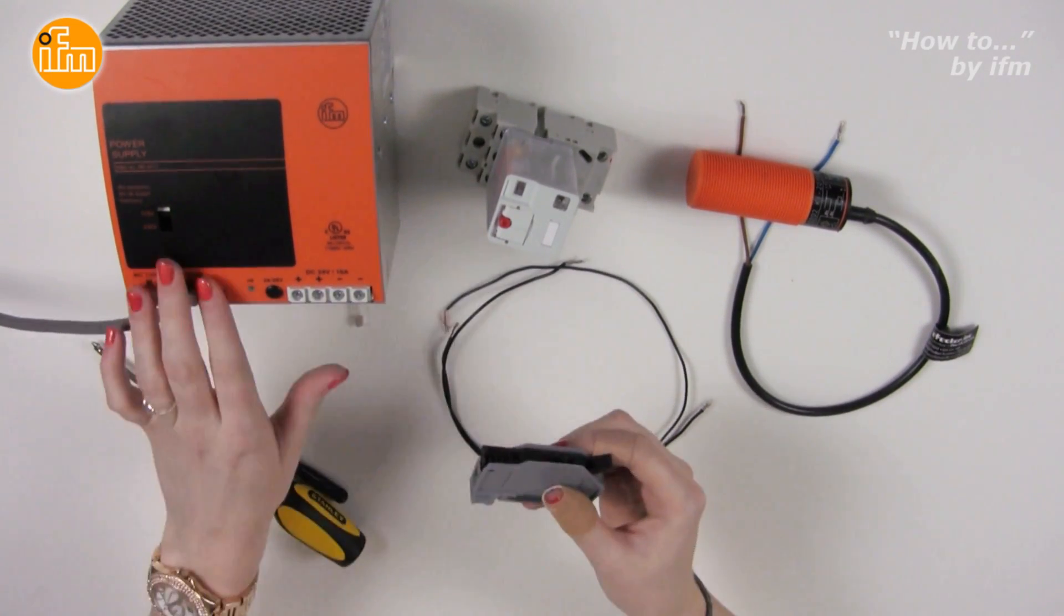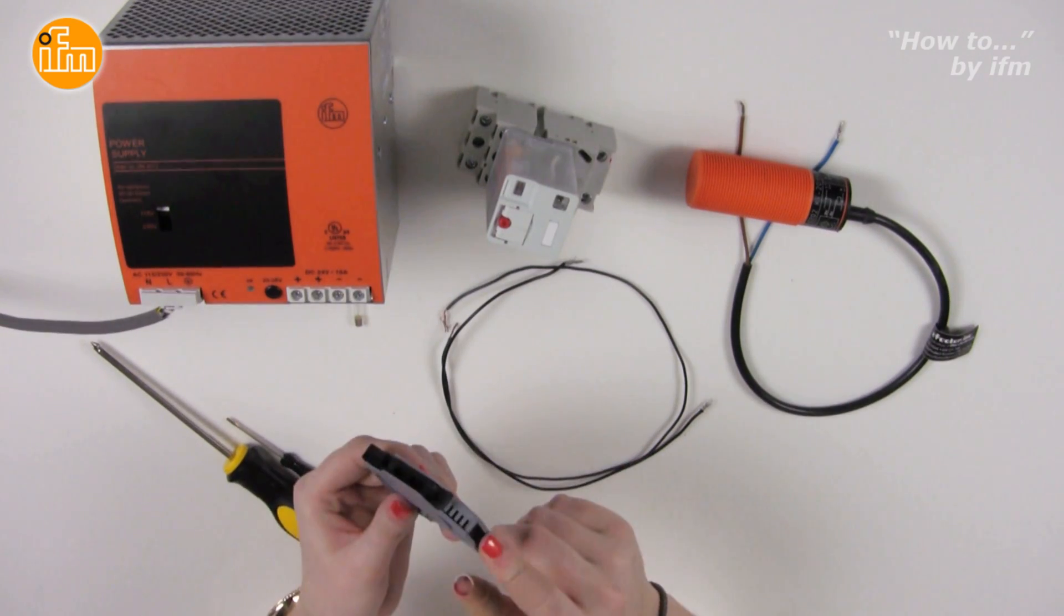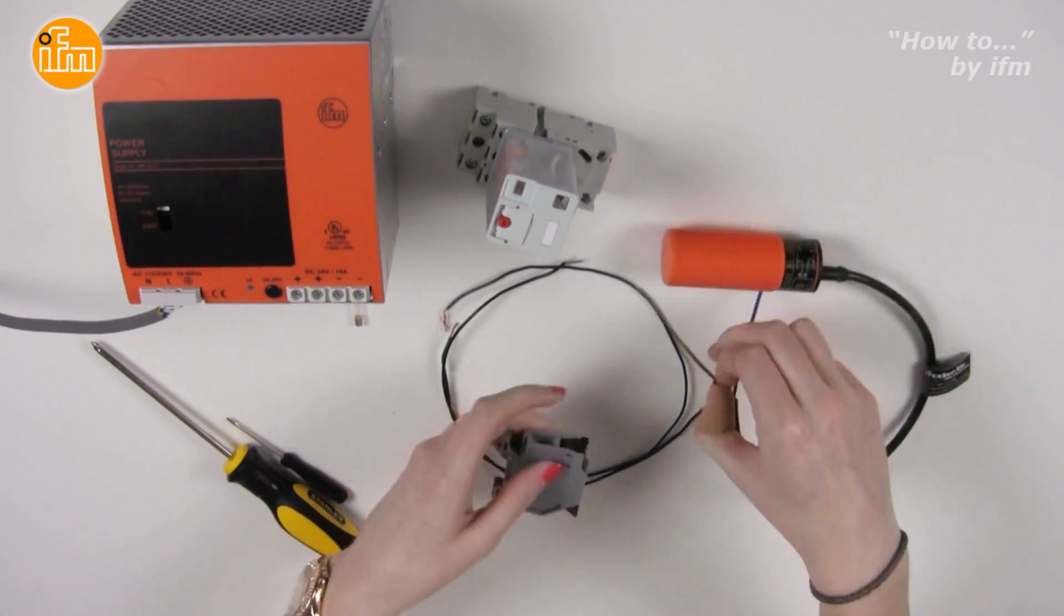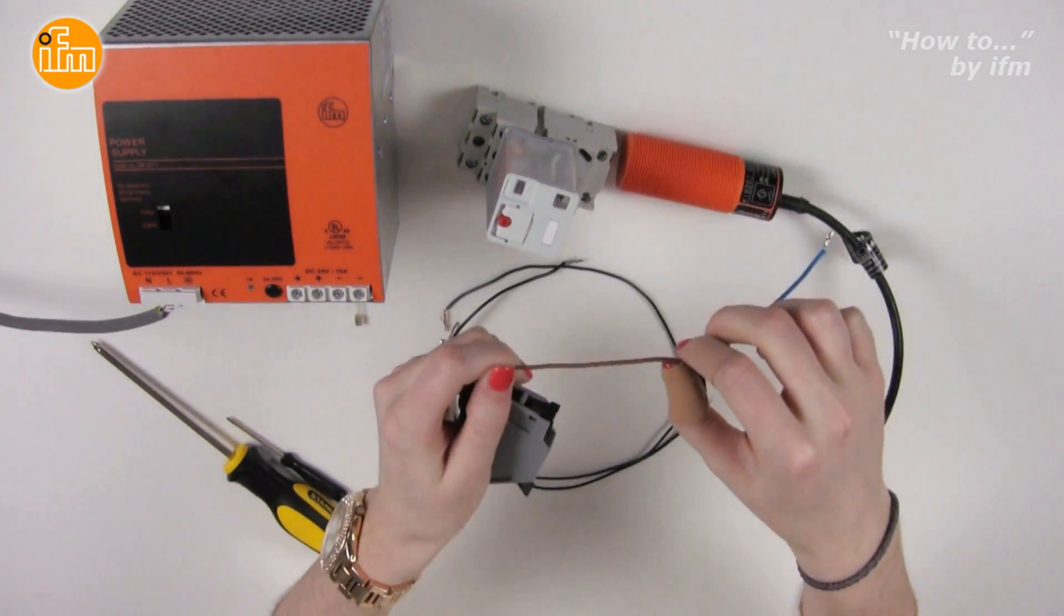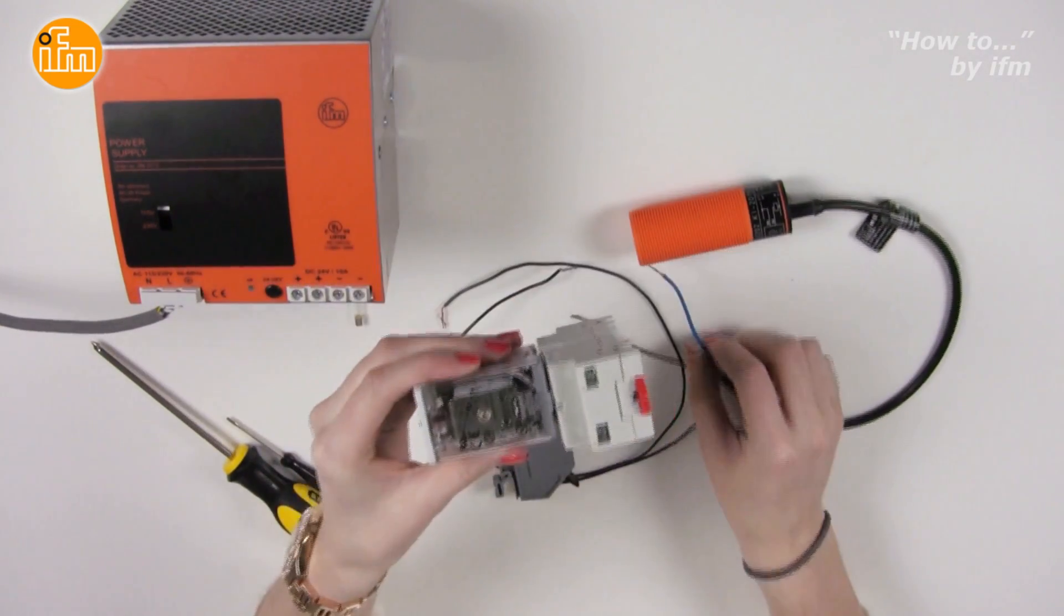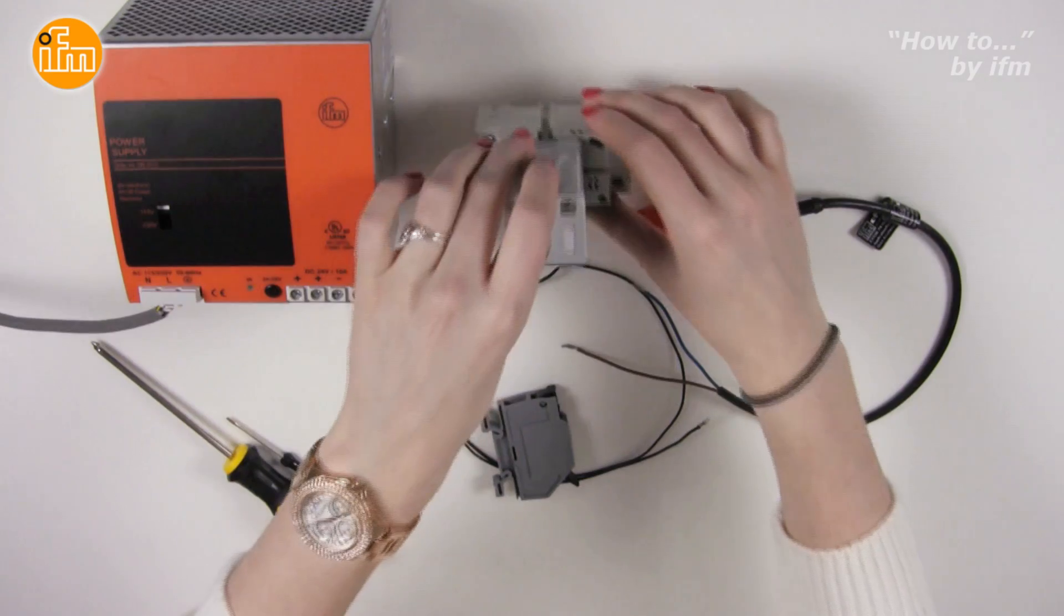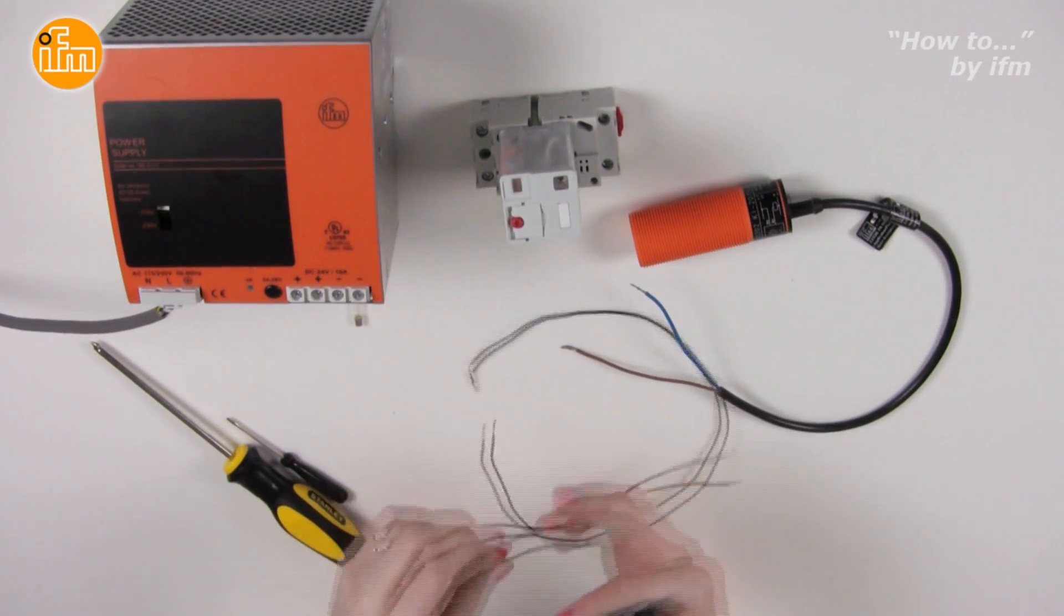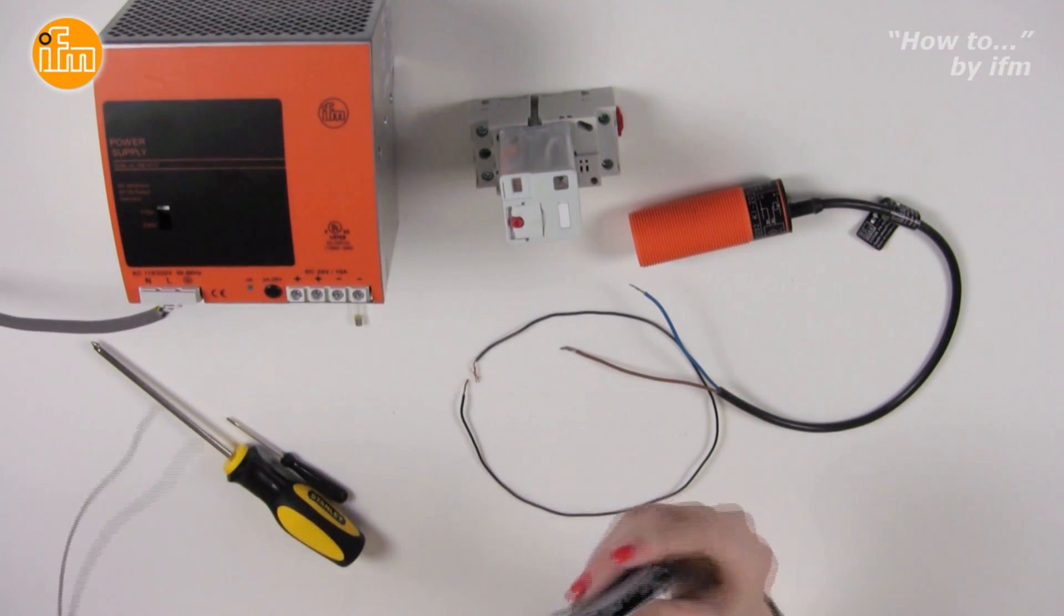The fuse should be on the hot side of the sensor, therefore the wiring will be from the L terminal, live or hot, of the power supply to the fuse. Next, the fuse is connected to the brown wire of the sensor, then the blue wire of the sensor will go to the relay, and then the relay will go back to the N terminal, neutral, of the power supply to complete the circuit.